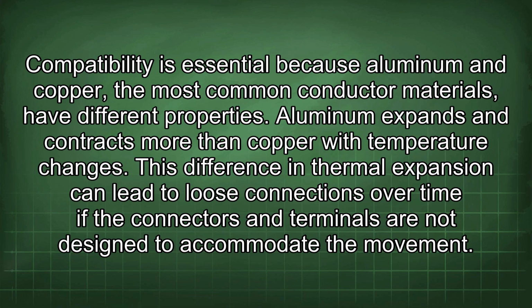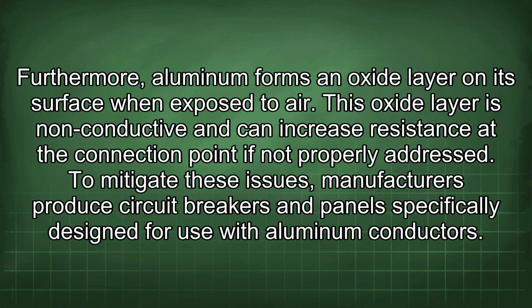Compatibility is essential because aluminum and copper, the most common conductor materials, have different properties. Aluminum expands and contracts more than copper with temperature changes. This difference in thermal expansion can lead to loose connections over time if the connectors and terminals are not designed to accommodate the movement. Furthermore, aluminum forms an oxide layer on its surface when exposed to air. This oxide layer is non-conductive and can increase resistance at the connection point if not properly addressed.